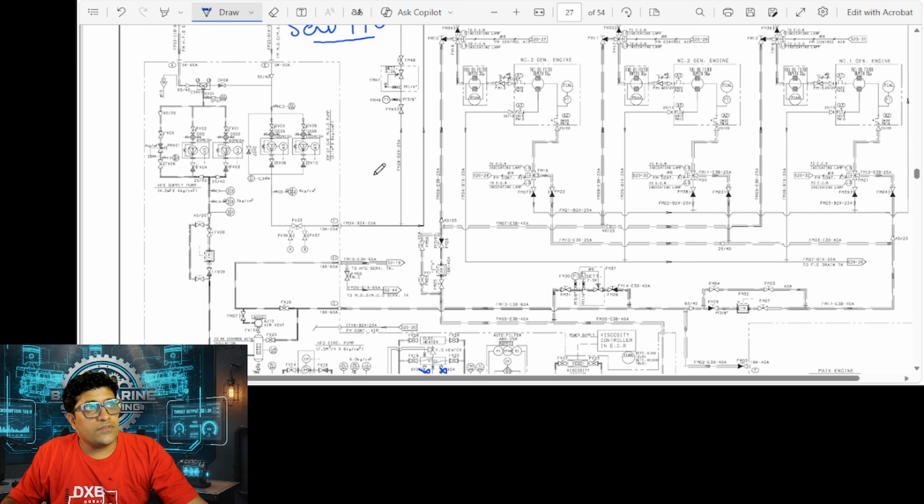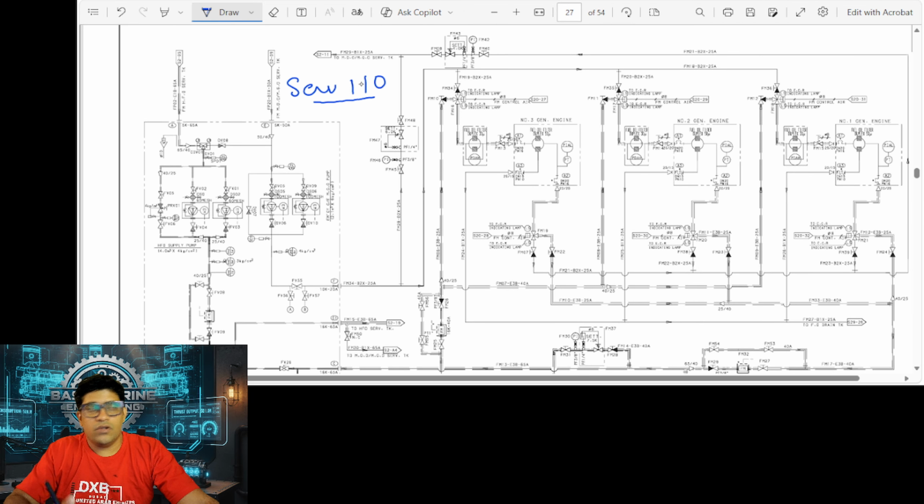If the service tank temperature was higher, you will also stop the steam for that earlier. You will try to maintain the temperature around 95 to 98 degrees, within that range. Once the temperature starts coming down, usually in about 45 minutes, say 9:30 or 9:45, the first step is to open the diesel oil valve. This valve is called the changeover valve. So you open this valve.